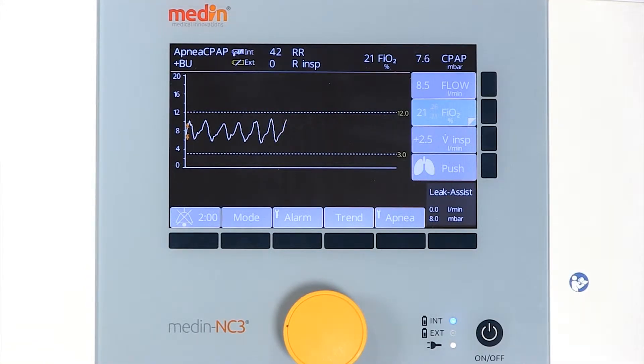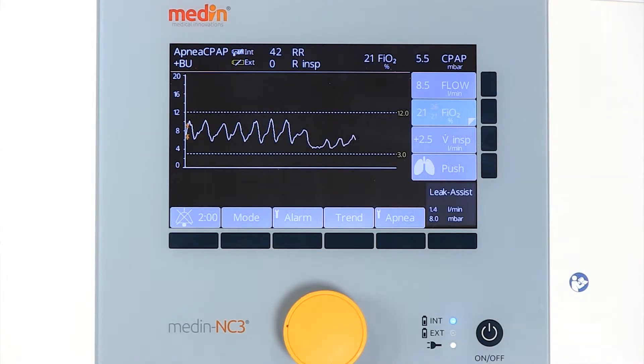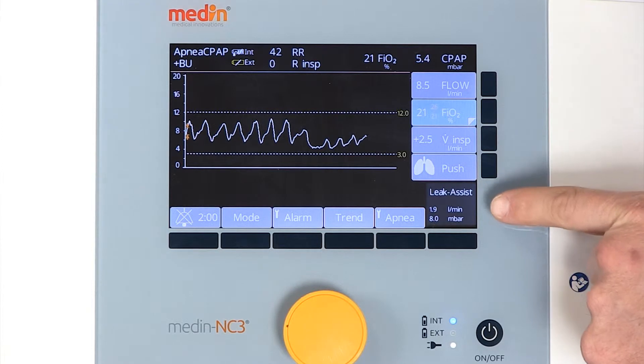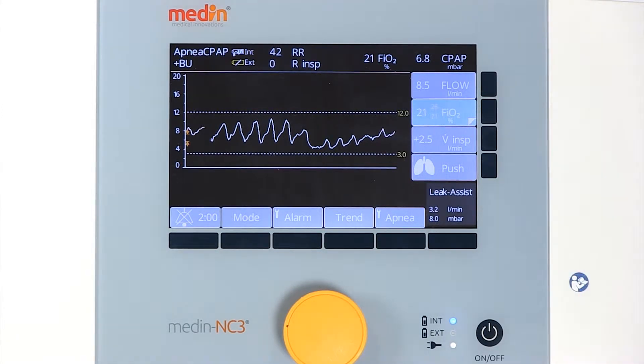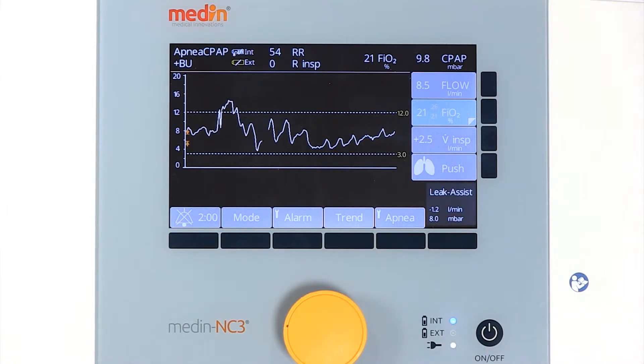If there is a difference of more than 0.5 millibars from the target pressure, leak assist will increase or decrease the flow to maintain the target pressure. The Medin NC3 compensates leakages with flows of up to plus or minus 5 litres per minute around the set target pressure.